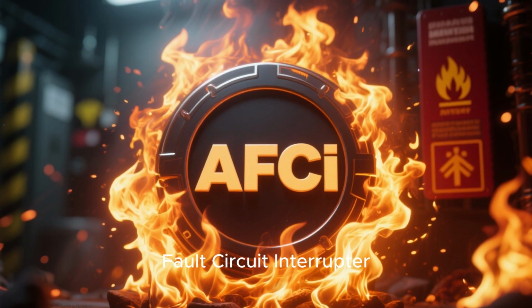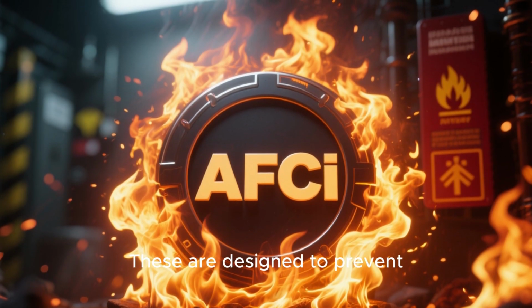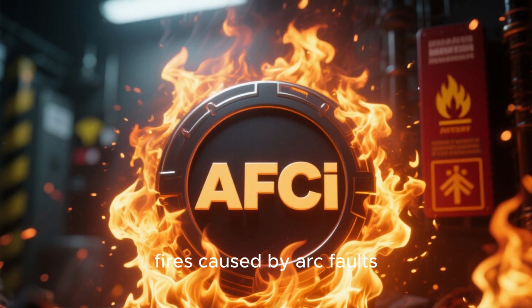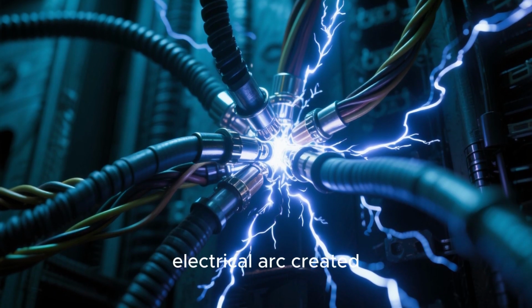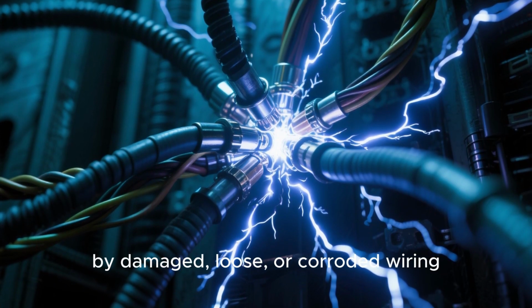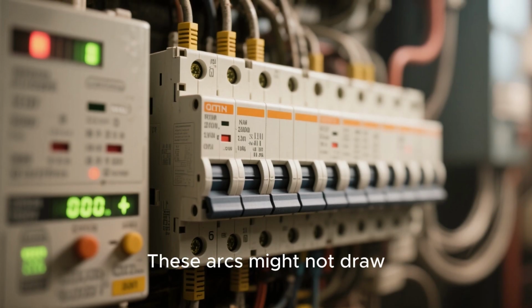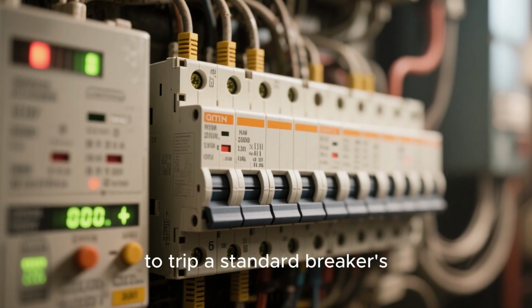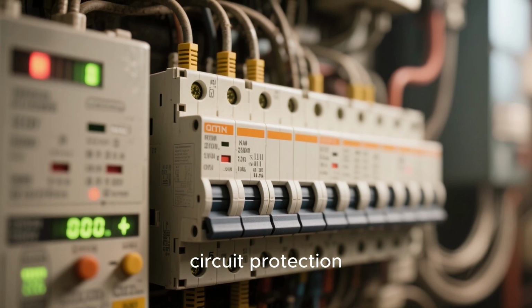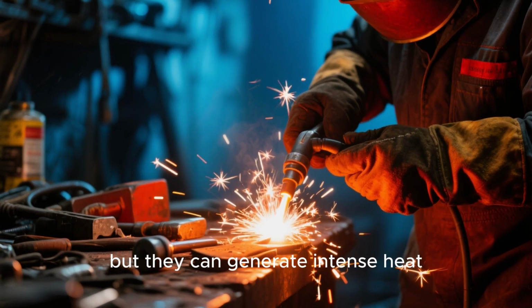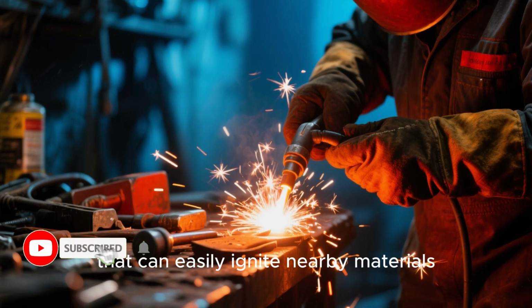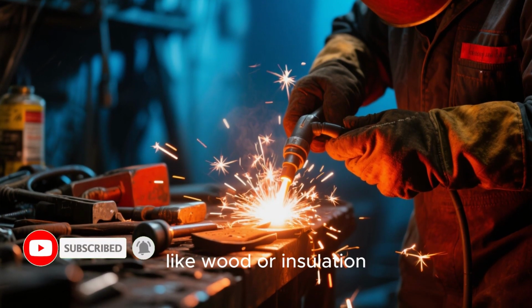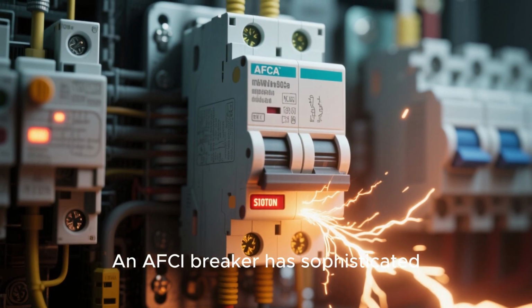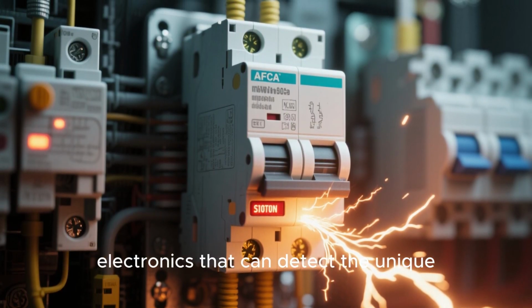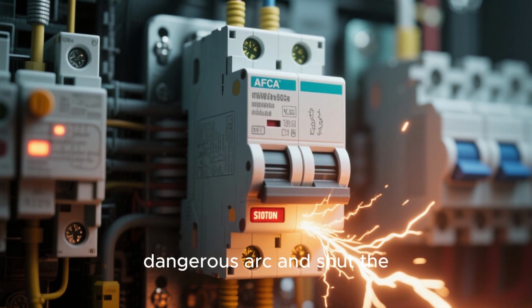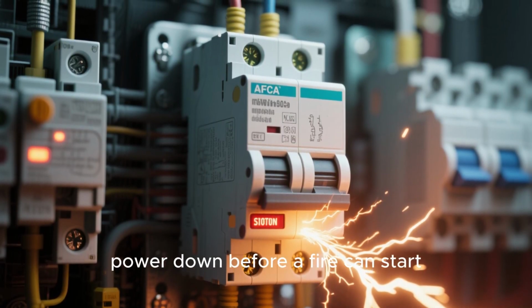AFCI stands for Arc Fault Circuit Interrupter. These are designed to prevent fires caused by arc faults. An arc fault is a dangerous electrical arc created by damaged, loose, or corroded wiring. These arcs might not draw enough current to trip a standard breaker's overload or short circuit protection, but they can generate intense heat, like a tiny welding arc, that can easily ignite nearby materials like wood or insulation. An AFCI breaker has sophisticated electronics that can detect the unique electrical signature of a dangerous arc and shut the power down before a fire can start.